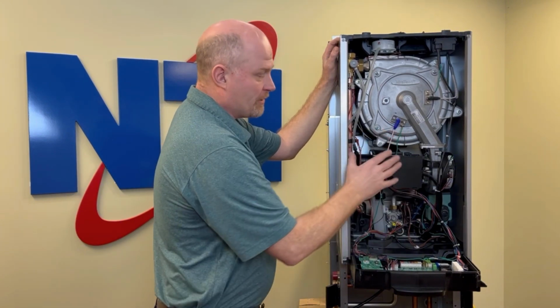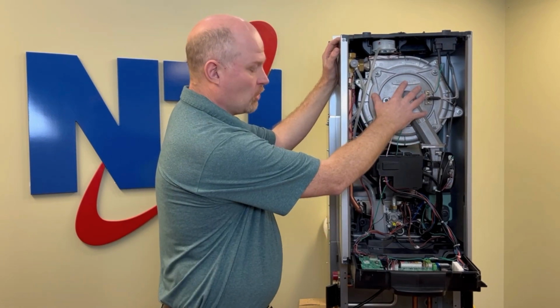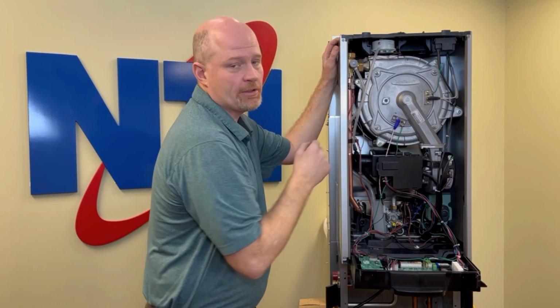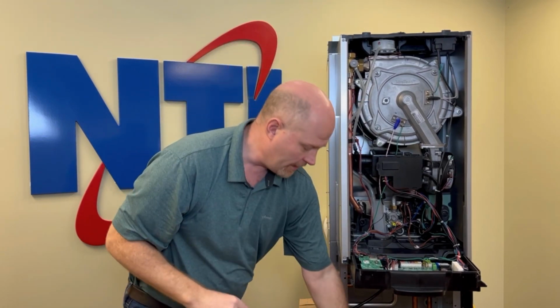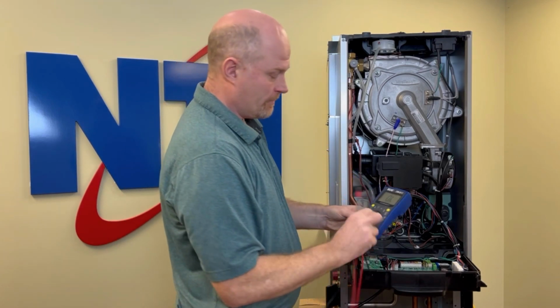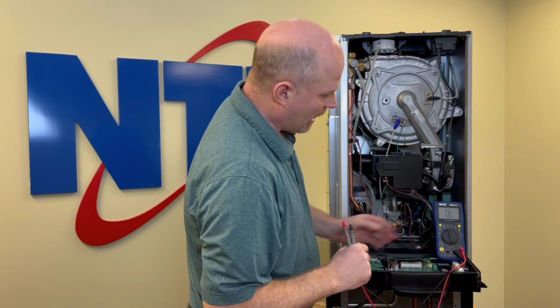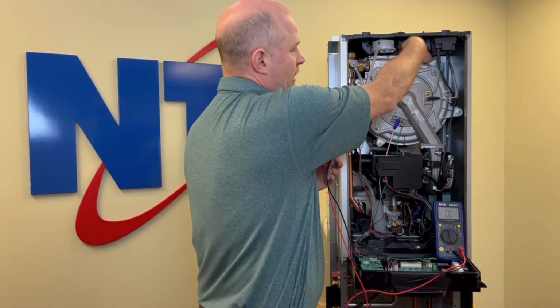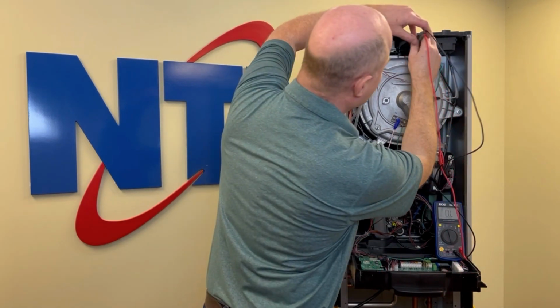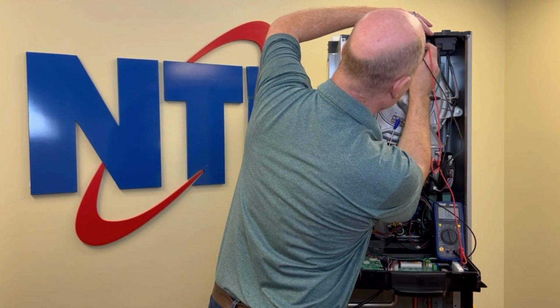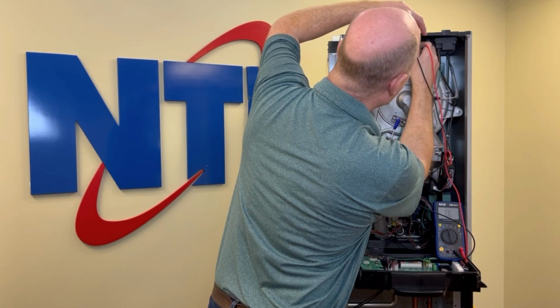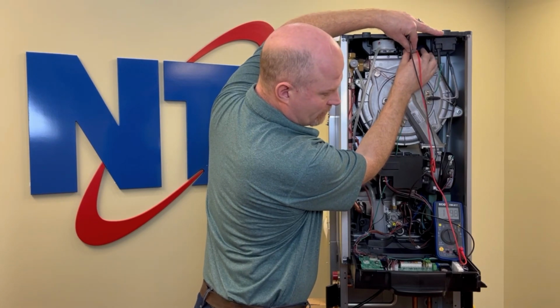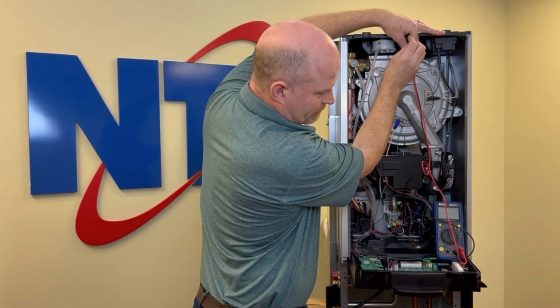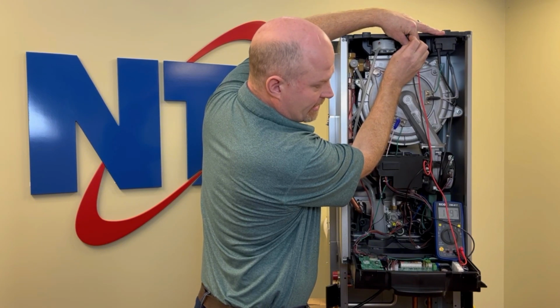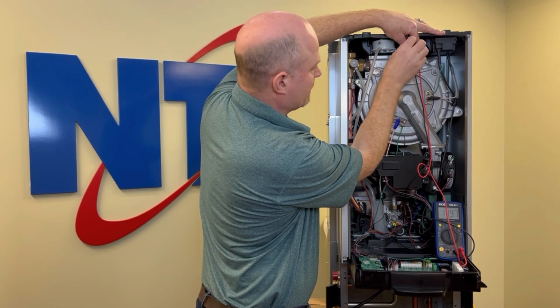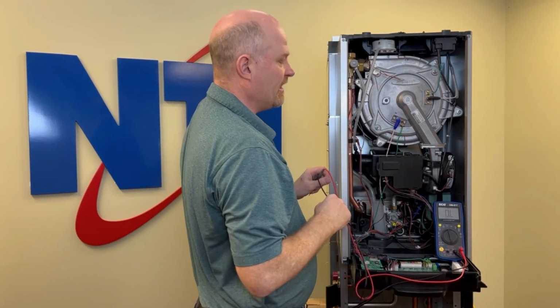Once you've verified that everything is okay with the boiler, there is no air, perhaps it's not genuinely overheating, the next step would be to test the sensor, and this also applies to error 605. To do this, grab your voltmeter, and you're going to want to set it to the ohms reading. And what I like to do is reach up, disconnect the plug from the sensor, and carefully test across the sensor for resistance. You can do this by touching 1 meter lead to each of the probes. Use care not to push too hard so you don't bend the wires, and see what you get for a resistance reading. In this case, I get a reading of just shy of 12,000 ohms of resistance, which for a room that's about 68 degrees is about correct.